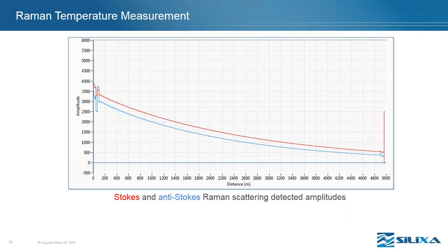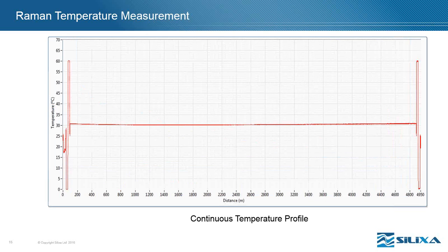of time. The output from the DTS, we capture both the Stokes and anti-Stokes Raman scatter detecting amplitudes as a function of distance. And within the unit, we calculate the temperature profile. The principle we are using to accurately locate the different temperature events across the fiber is a technique called the time of flight.